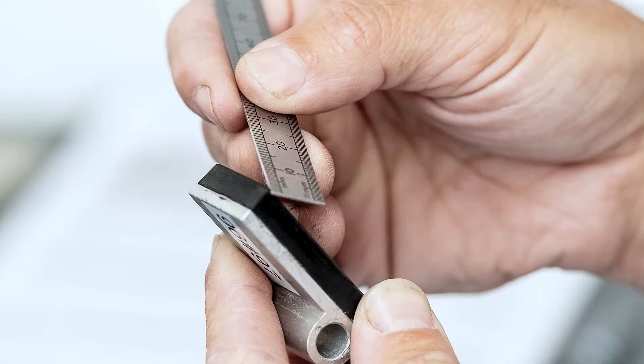Regardless of your needs and before every test, a technician will check the integrity and quality of the rubber slider as a further guarantee of accuracy, measuring the contact edge to ensure it is between the specified 1mm and 4mm range.